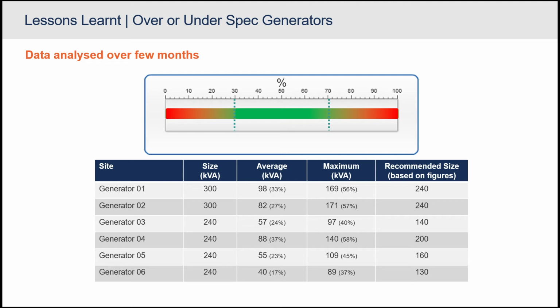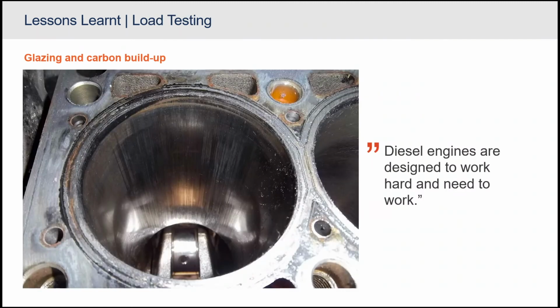Just some nice information - slide after this talks about what happens if you don't run a diesel generator to its capacity. There's a saying that diesel generators are designed to work hard and need to work hard, and that is very true, because you get typical glazing and carbon buildup if you don't. That's actually quite an interesting topic when you unpack it - the reasons why it happens and what the result is. But as I said, it absolutely reduces your expected asset life dramatically.